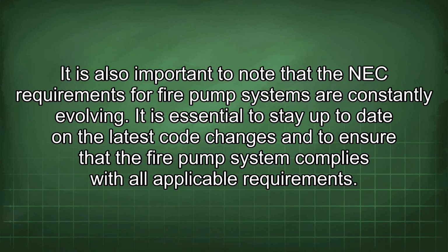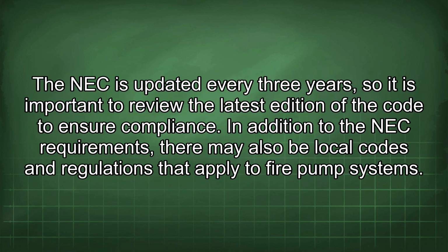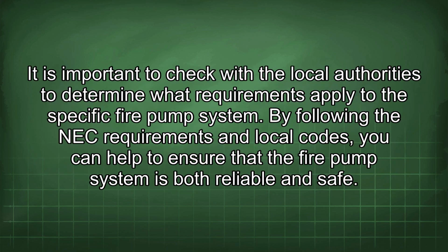It is also important to note that the NEC requirements for fire pump systems are constantly evolving. It is essential to stay up to date on the latest code changes and to ensure that the fire pump system complies with all applicable requirements. The NEC is updated every 3 years, so it is important to review the latest edition of the code to ensure compliance. In addition to the NEC requirements, there may also be local codes and regulations that apply to fire pump systems. It is important to check with the local authorities to determine what requirements apply to the specific fire pump system. By following the NEC requirements and local codes, you can help to ensure that the fire pump system is both reliable and safe.